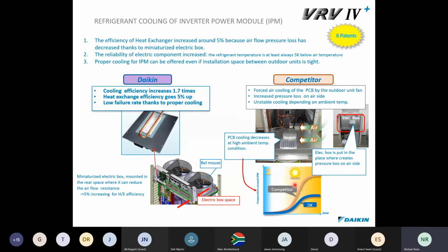So also we have the refrigerant cooling. We've also had that on our VRV IV. The efficiency of the heat exchanger is increased by around 5% because of the airflow pressure loss that I explained earlier, and the reliability of the electrical components is also increased. The refrigerant temperature is always at least 5K, or 5 degrees, below the air temperature. And the proper cooling for the inverter power module can be offered even if the installation space between the outdoor units is tight. Looking at our competitor and at us, our cooling efficiency increases about 1.7 times, our heat exchanger efficiency goes up by 5%, and we have a lower failure rate thanks to the proper cooling.